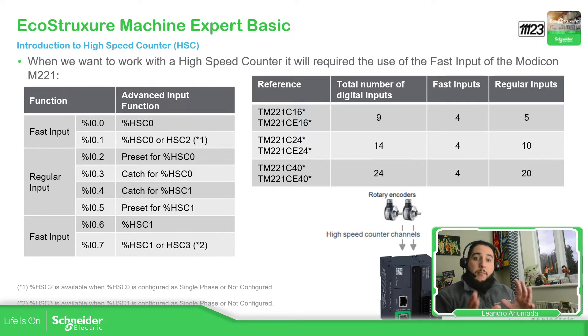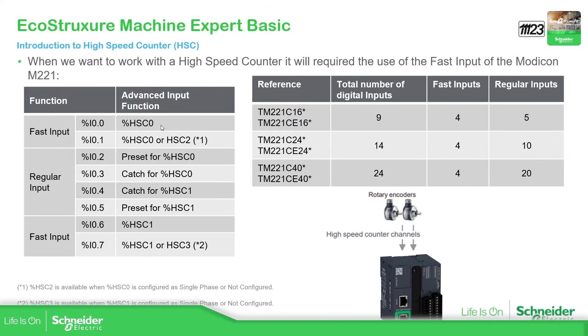Here you can see the assignation of the digital inputs of the M221 for fast inputs. We have the first two inputs and then the last two — inputs six and seven — which are related to high-speed counter one, and inputs zero and one are for high-speed counter zero.